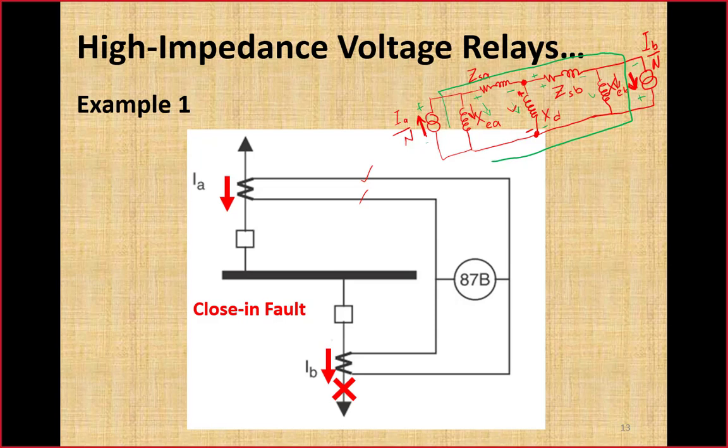So it will circulate in the outer loop. Again, if everything is ideal, no CT gets saturated and CTs are producing equal, or you can say perfect, replica of this fault current on the secondary side, the behavior of this relay during normal condition and during close in external fault will be same, no problem at all. This differential branch would carry zero voltage.